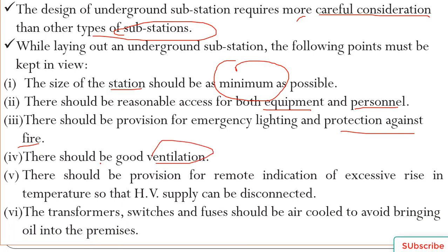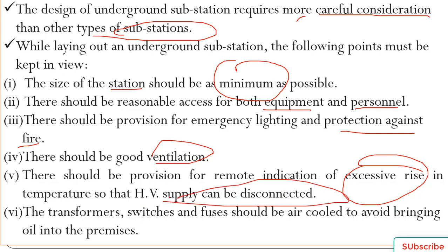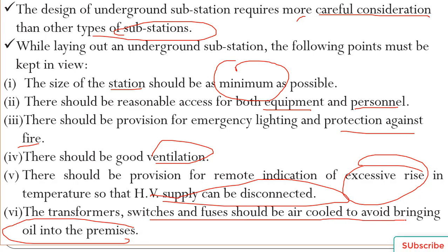There should be good ventilation. There should be provision for remote indication of excessive rise in temperature, so that the high voltage supply can be disconnected to protect against any fault. The transformer, switch and fuse should be air cooled to avoid bringing oil into the premises. It must be cooled with air.